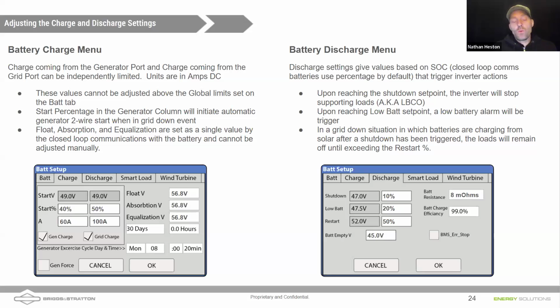Now, remember, if you are running a smaller generator and that generator comes on when a charge cycle is enabled on the batteries, you might not have enough solar to cover your loads. The generator has to cover the loads and the charging of the batteries. So you might want to limit how much charging you do so you don't overtax your generator, stall it out, or just overdo it. On the grid side of things, the same thing.